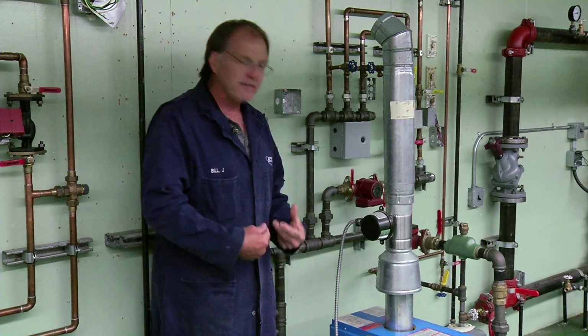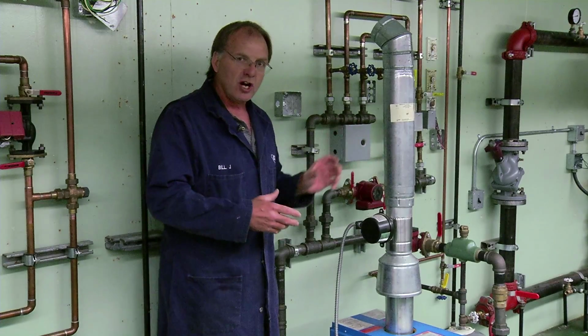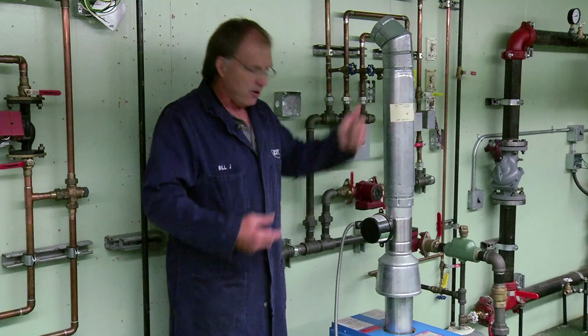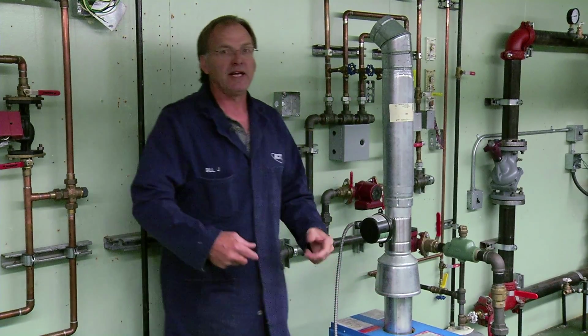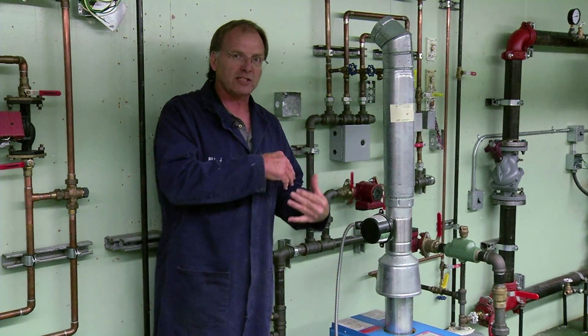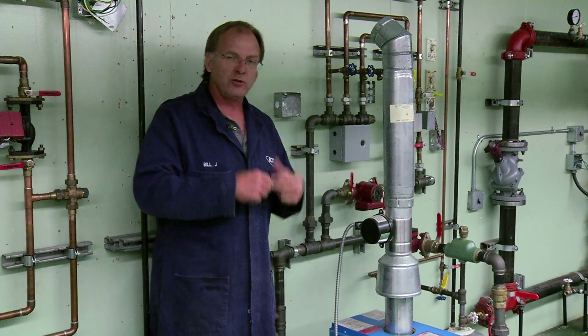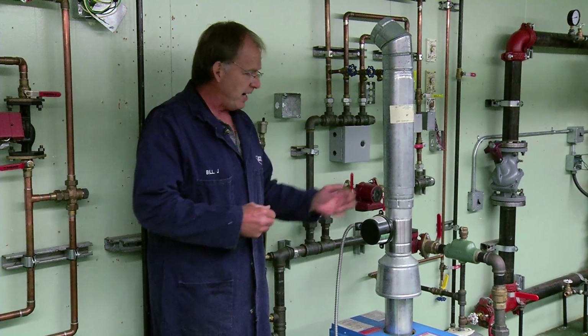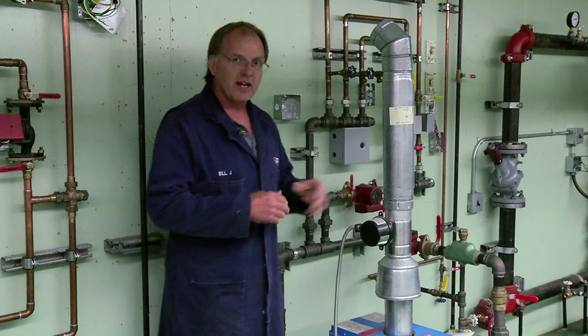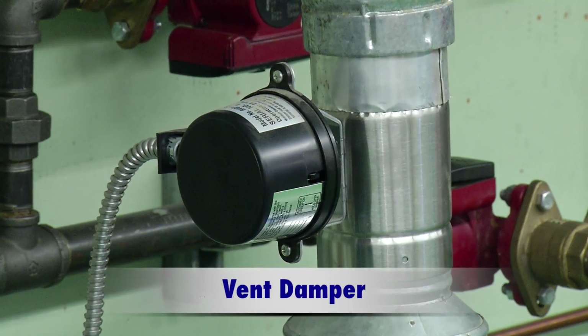Inside a house, we've heated the air, we've heated the house up, and there's actually money in the energy that we have in there. When this boiler is not firing, there still will be convection currents causing air to come through these dilution openings and outside. That is a loss to the client. So what we want to do is prevent that. And we did that around the 80s when we developed what we call a vent damper.